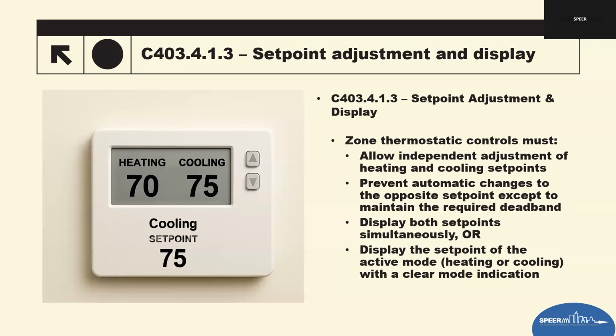So the thermostat must be able to display both heating and cooling set points at the same time, or display the set point for the active mode and show which mode is currently active. For example, if it's in cooling, the set point shows 75. This prevents confusion from the occupants and occupiers and ensures system behavior is transparent. This section also ensures that occupants clearly understand that heating and cooling thresholds prevent accidental crossover and supports the required deadband. So it also prevents manufacturers from using simplified thermostat interfaces that hide one mode's set point. Basically something that's happened in the past with other code compliance issues.